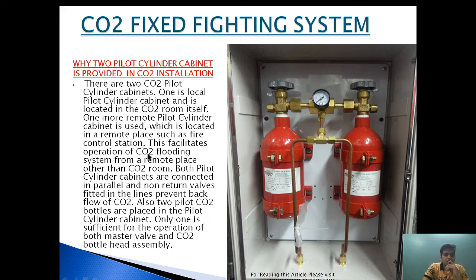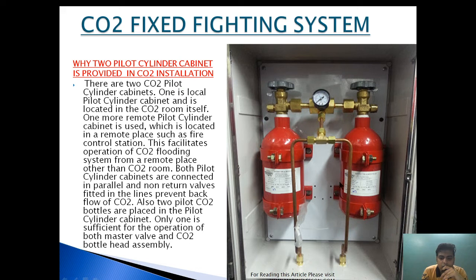For remote operation of the CO2 flooding system from a place other than the CO2 room, both pilots in the cabinet are connected in parallel. A non-return valve fitted in the line prevents back-flowing of the CO2. Two pilot bottles are placed in a pilot cabinet, and only one is sufficient for operating both the master valve and the CO2 bottle head assembly. A pressure gauge is provided, showing around 56 bar, and an individual unit is sufficient to activate or puncture the CO2 bottle.